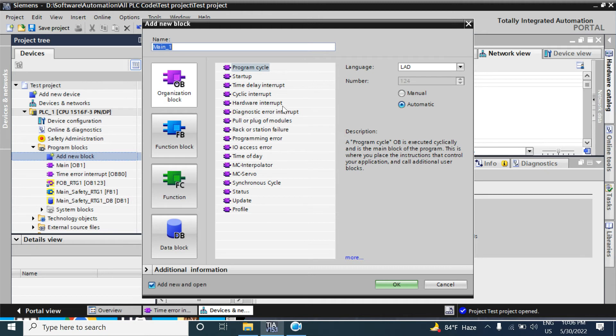The next OB is Diagnostic Error Interrupt. This is called by your CPU when a wire break, short circuit, or missing supply is detected in your module. It is not normally enabled — you have to enable it by configuration, and it is not available for all CPUs. If you do not call this OB in your program, the CPU will just ignore the diagnostic error and will not go to stop mode.